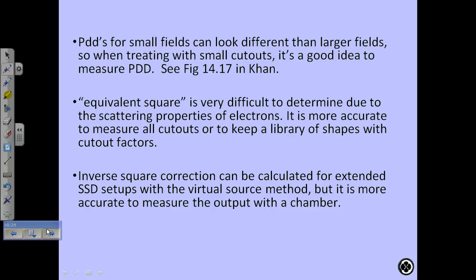Here we go. So, field size. They have 2 energies here. They have an example of an 8 MeV electron curve and then a 32 MeV. This is pretty high, 32 MeV. That's probably from a betatron or something, not from a regular Linac. But anyway, what tends to happen if your field size gets smaller is that your PDD starts to come back. It starts to get shallower and not as penetrating as your aperture gets smaller.